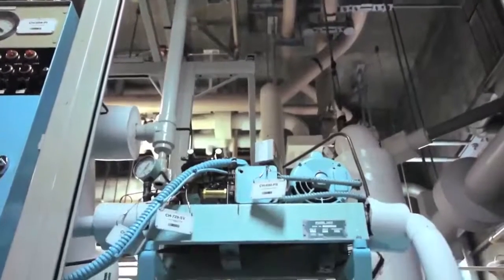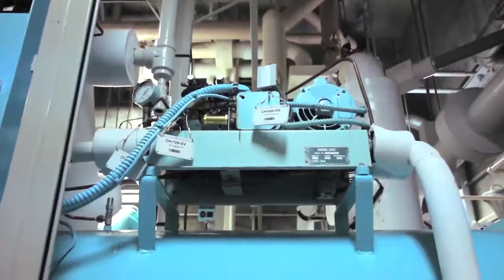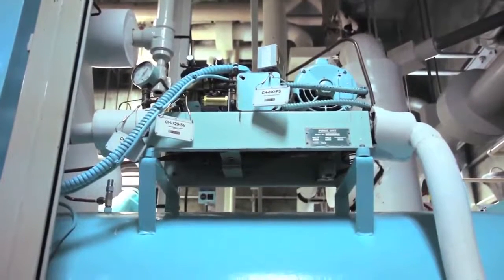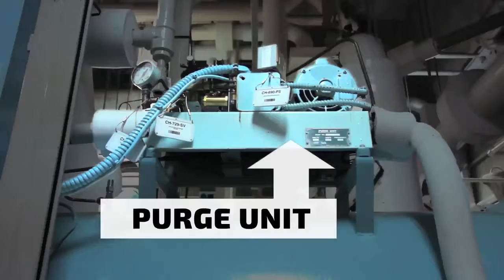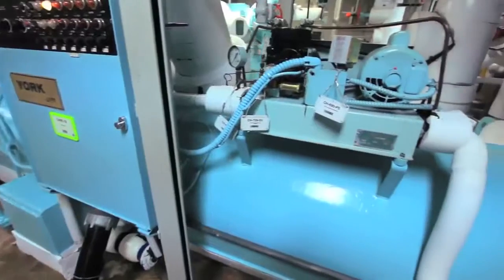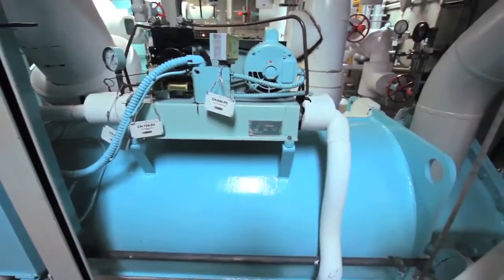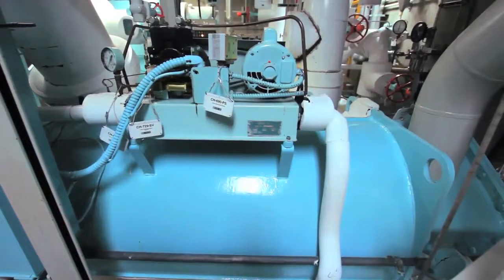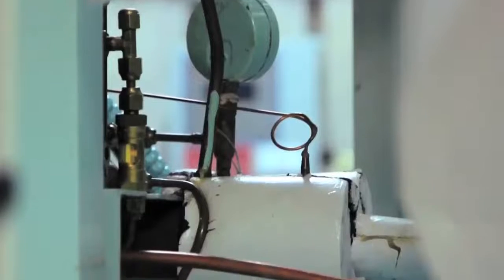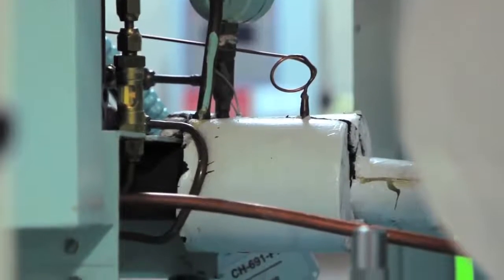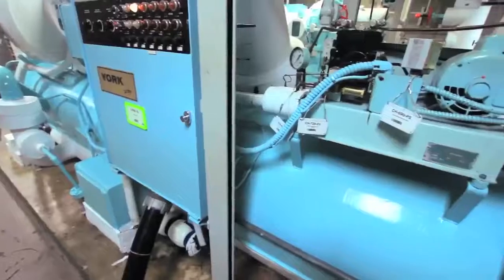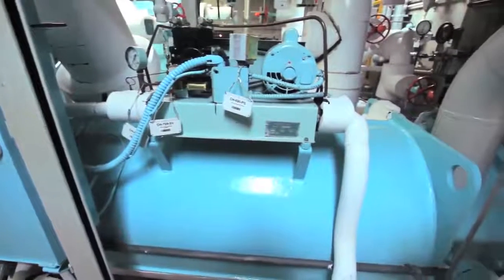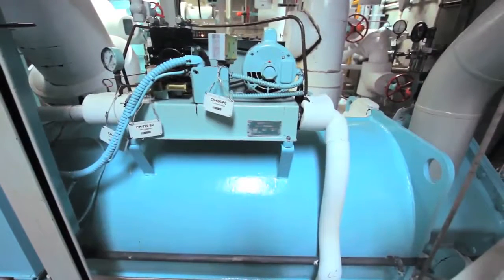When these machines were originally designed, a certain amount of air leakage was expected, which was compensated for by the addition of a purge unit. Non-condensables are gases normally found within the atmosphere which will not condense during normal operation. This purge unit takes refrigerant along with non-condensable gases, then condenses the refrigerant out of the non-condensable atmospheric gas. The liquid is returned to the refrigerant system and the non-condensable gases are discharged to the environment.